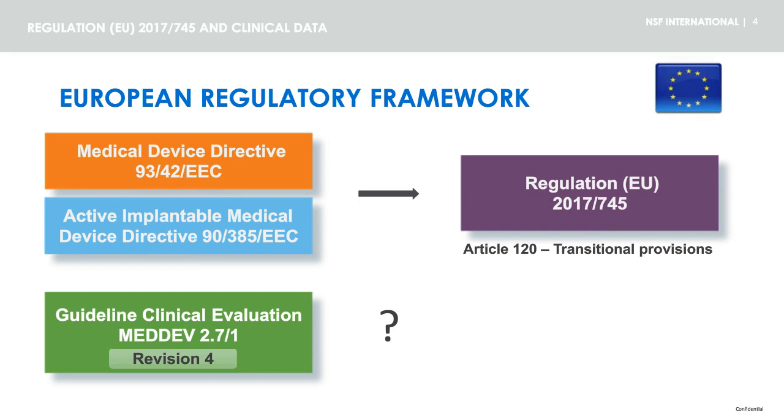The European Union also has several medical device guidelines. One example is the Guideline on Clinical Evaluations, MEDDEV 2.7/1 Revision 4, the content of which refers to the current directives. With the regulation in place, guidelines referring to the directives are officially repealed. Therefore, a new revision of this guideline and/or additional guidelines of the European Commission are needed for further guidance on clinical evaluation.